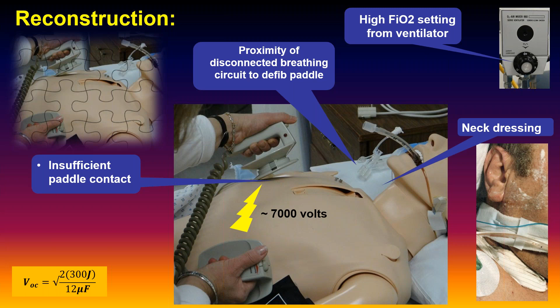But again, these older defibs, the old HP defibs, have an open circuit voltage of about 7,000 volts. There's some serious juice there, right? And so with a poor contact, that's what caused the arc: the endotrach tube, the vent, they disconnected the ventilator. Anyway, we reconstructed this for the insurance because it's instant lawsuits. They don't even go to court on this kind of stuff. But they were dying to know how this happened. So we created this little scenario to show they disconnected the vent tube, blowing 100% O2 around this environment to spark the oxygen-concentrated environment, and that's what put it all together. But it took a whole bunch of time, a couple of months at least, not more, to do that.